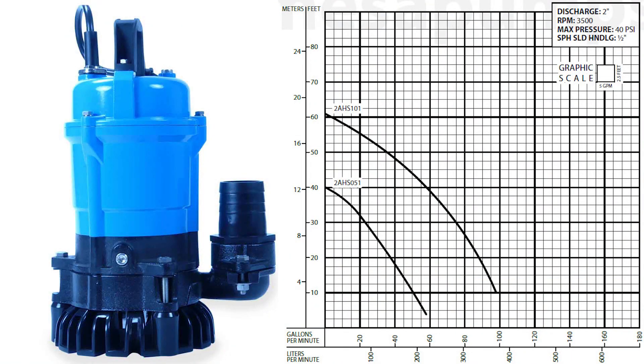At the standard 3500 RPM, the half-horsepower model can produce 40 feet of head and a maximum flow rate of 59 gallons per minute. The one-horsepower model can produce 61 feet of head and a maximum flow rate of 98 gallons per minute.